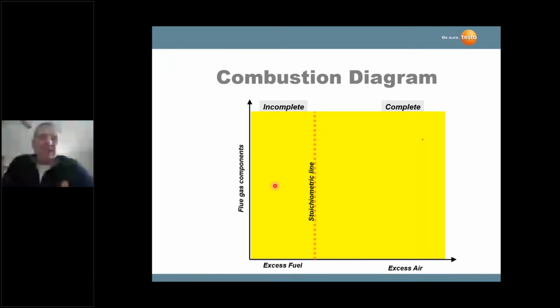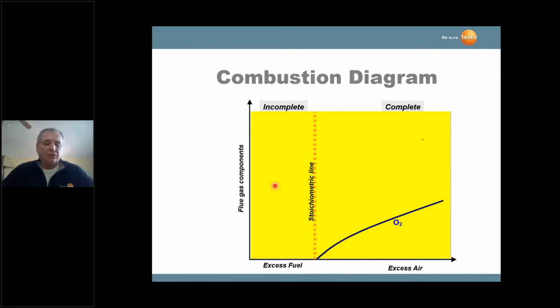It's important that we know the relationships of gases in the flue gases. The reason why is instruments today, whether you use a Testo or someone else's, is a quite easy instrument to use. You can turn it on, it goes through a power up, it does its own checkout of the instrument, and then when you're ready to go into the flue gases and look at the readings, you're going to get a lot of these readings simultaneously. And I just want to go through some of these readings with you.